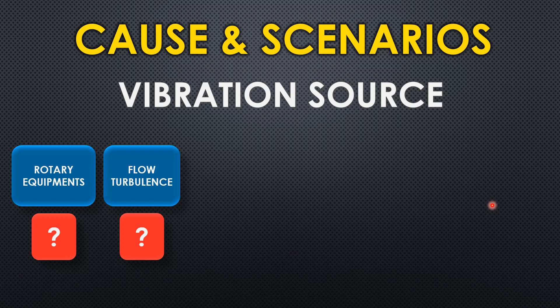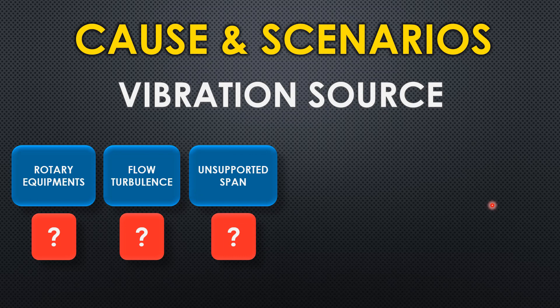Generally the first step to minimize flow turbulence is process design, then mechanical design. The third vibration source is unsupported span. If your line is not supported properly, you can expect vibration in that portion because the span of a piping system is calculated based on various factors including vibration. If you don't provide pipe support at appropriate span intervals, the pipe will move where it is unsupported.